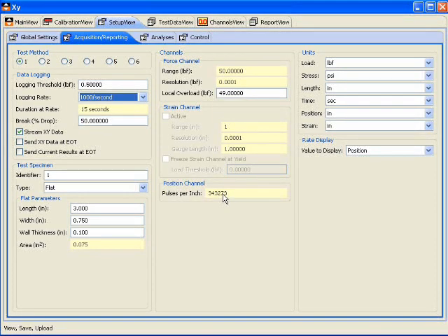This is a demonstration on how to set up a test using the XY software. Under the Setup view and then the Acquisitions slash Reporting tab, we can set up our test. Test method, we have 6 test methods we can program at once. The Q controller can handle the 6 test methods. The P controller can only have 1. So right now we'll just work on test method 1.